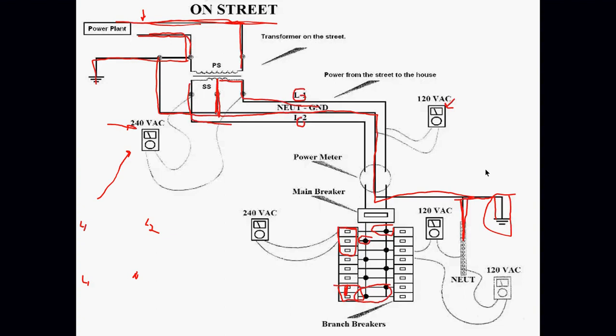Okay, now that causes problems. What happens when the city comes along and decides to replace that meter outside with a PVC pipe and meter with PVC piping? What happens to your ground? It goes away. So that's what I'm saying - some of this is out of your control, and the guy replacing that pipe in the yard with a PVC or plastic pipe doesn't know that your electrical circuit is grounded to that pipe. So you could all of a sudden no longer have a ground. Bad things happen, and you won't find out.